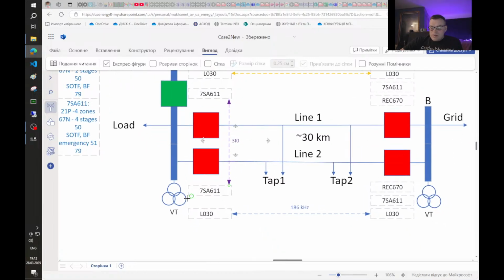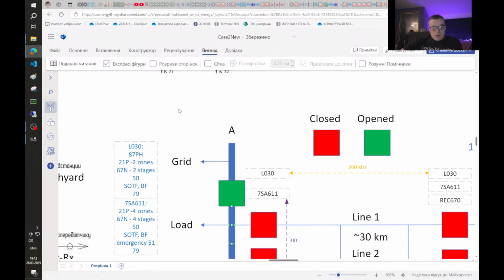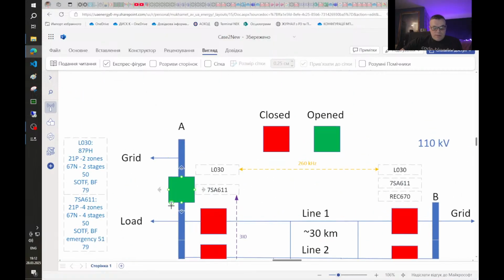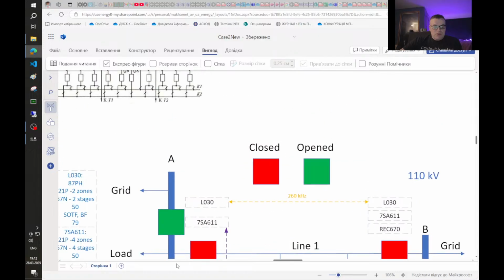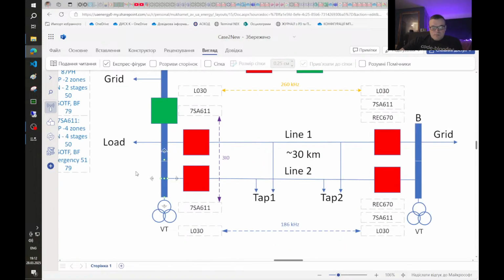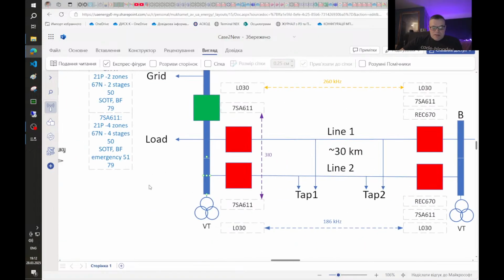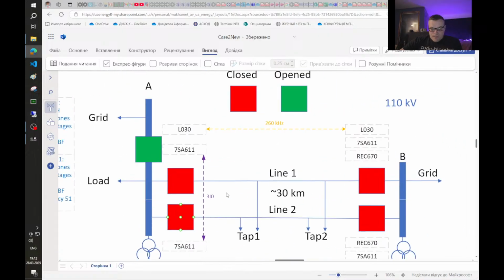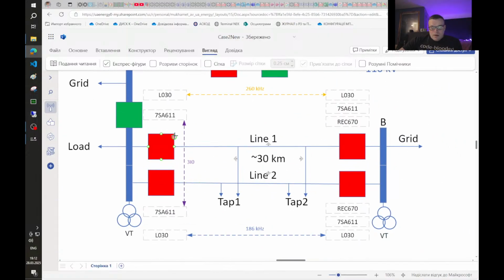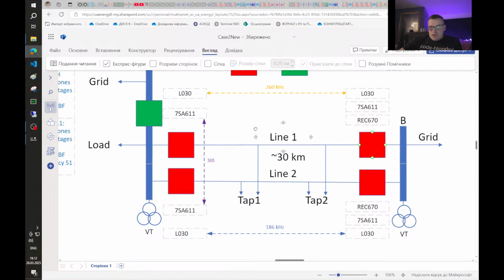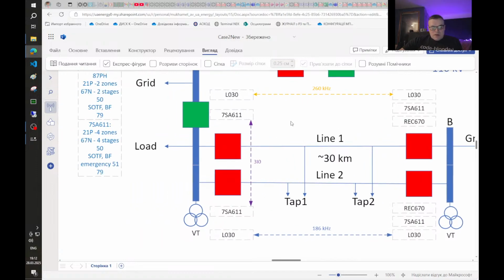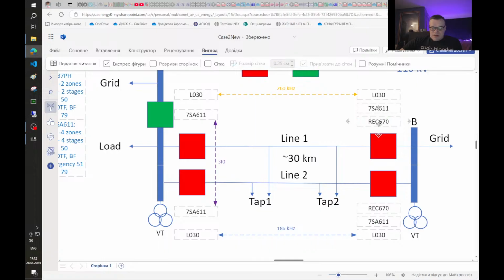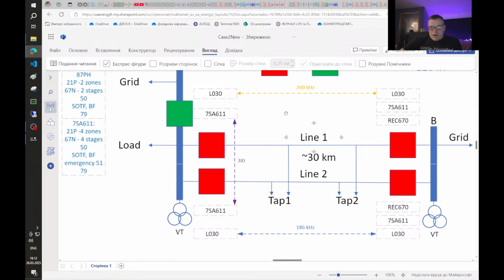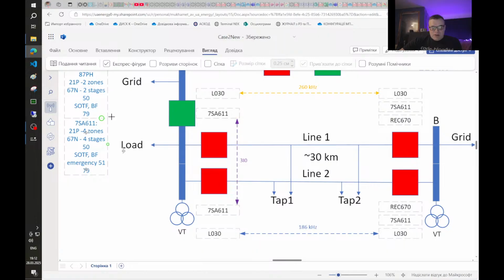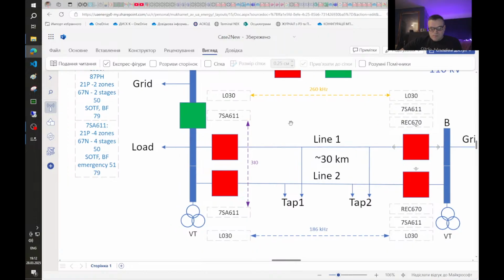And I want to add about the primary scheme a little bit. Usually with such a scheme, VTs are connected only to bus bars to make the scheme a little bit cheaper. From that side, it's pretty much the same, except that REC 670 has breaker failure protection and auto reclosing function.